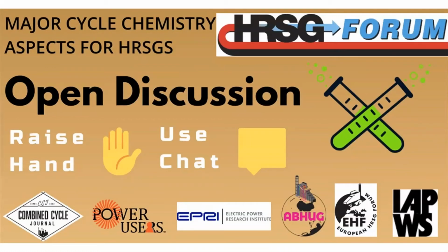Probably the biggest thing that anyone can do to help all of us is make sure there are opportunities for doing sampling and doing it properly. As I said in my presentation, we're assuming there are sample points and that everything's been taken into account, whether it's the right kind of sampling nozzles, or whether it's isokinetic or not. We assume that's done before we can even start any kind of analysis. So that's critical.